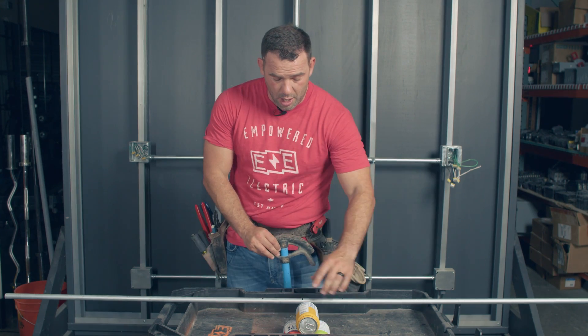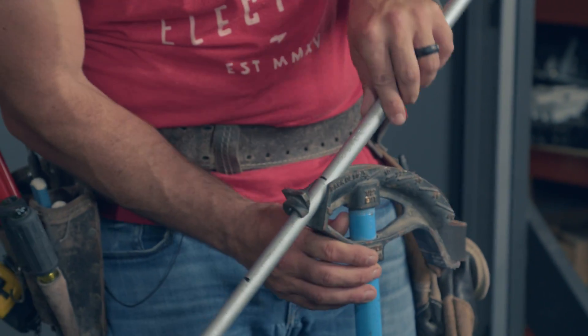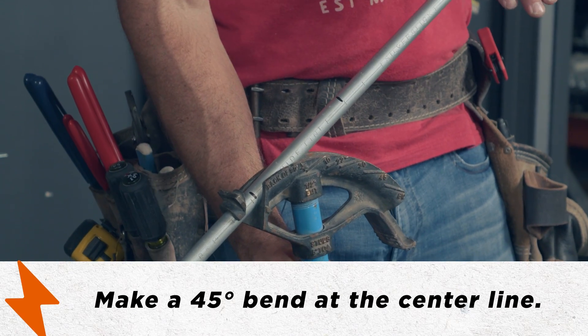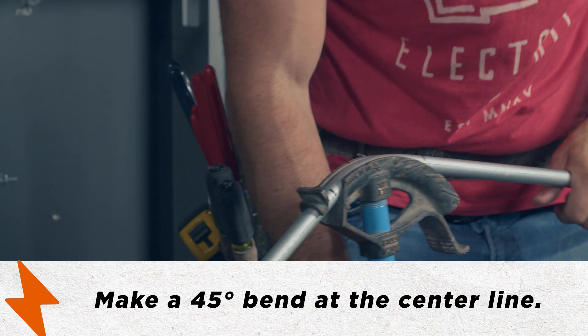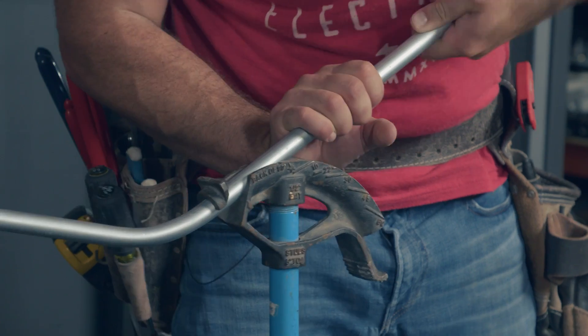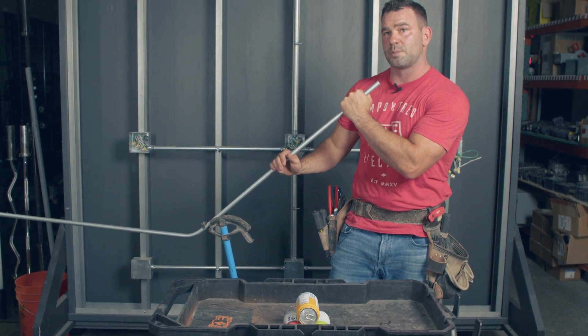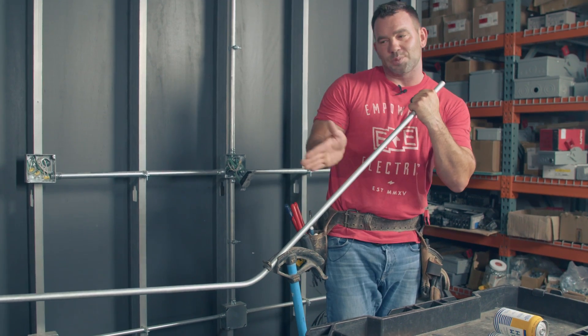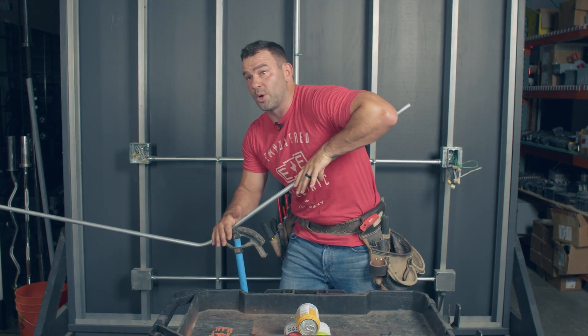Depending on which direction you're going, you start with the mouth and center line going the same direction. The center line is your first bend. Slide the conduit into the mouth of the bender — the mouth is where you feed the pipe in, the shoe is at the bottom — and bend to a 45-degree bend. Come down past 30, down to 45. Then pop it in and slide to your next mark.